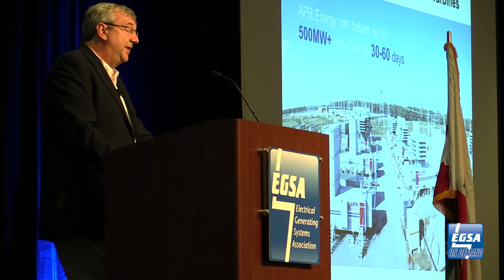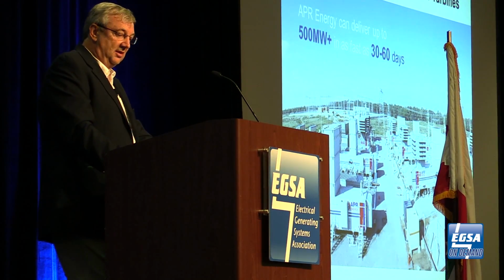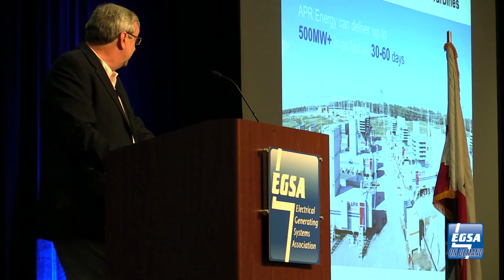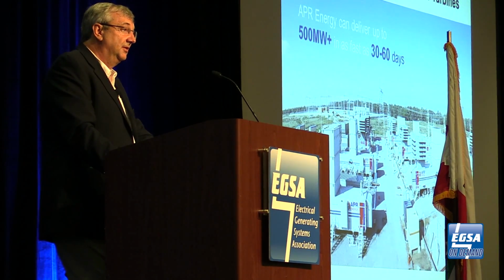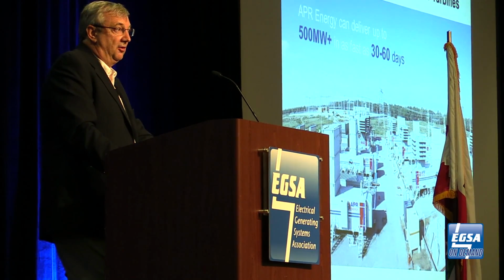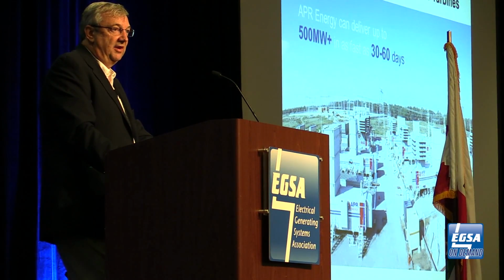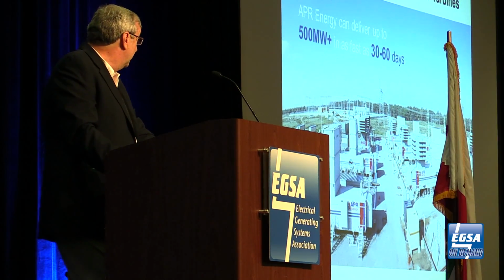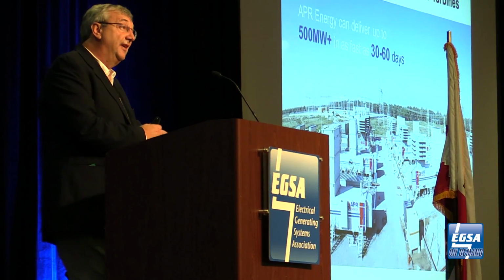There's all the engineering to go in behind that as well, doing grid impact studies, making sure that we don't impact the grid and the grid doesn't impact us. We don't have any issues with fault currents, that if something does go wrong, the devices can clear it. And we all know that when we're dealing with generators, we have to look at the sizing of the breakers on our generators, depending on the application, to make sure that the kA ratings are correct. If they're not, and there's a fault, the breaker doesn't trip. It's the exact same thing when we go in and look at large power plants. We have to evaluate that all the way through.